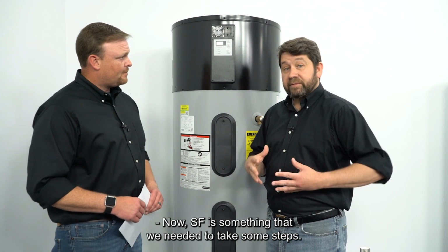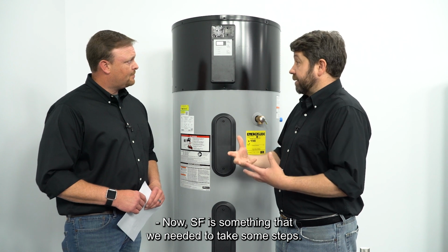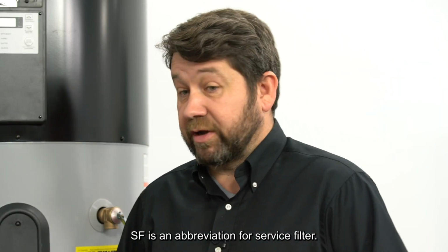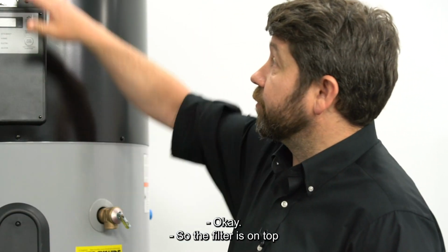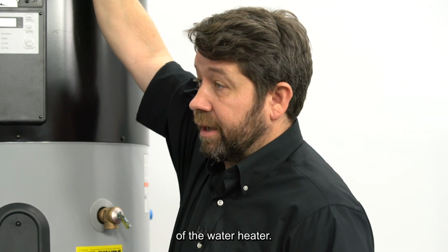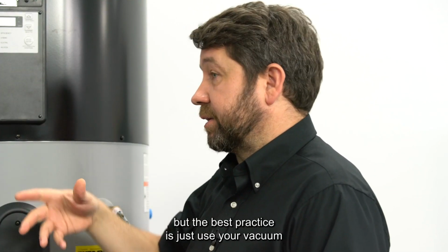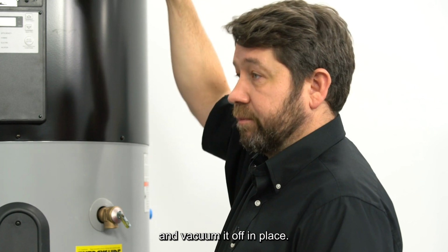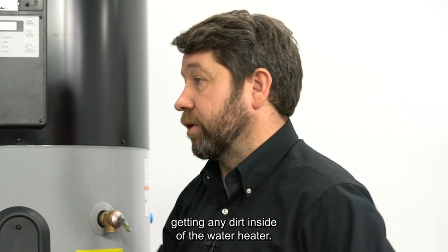Okay, how about the SF mode? Now, SF is something that we need to take some steps on. SF is an abbreviation for service filter. The filter is on top of the water heater. Now, you can remove the filter, but the best practice is to just use your vacuum and vacuum it off in place. That way we don't worry about getting any dirt inside of the water heater.